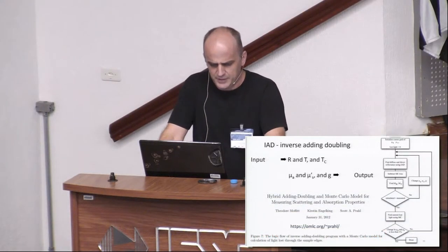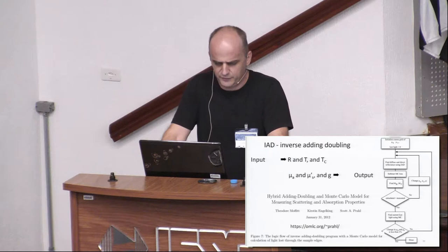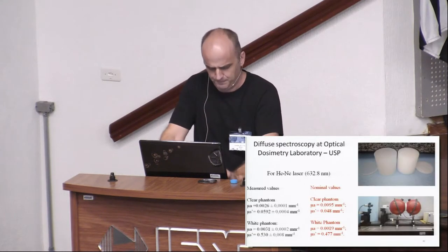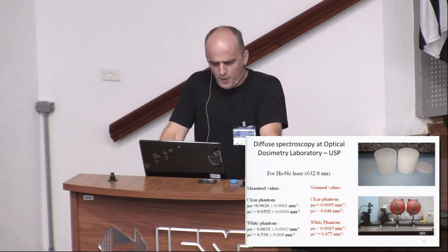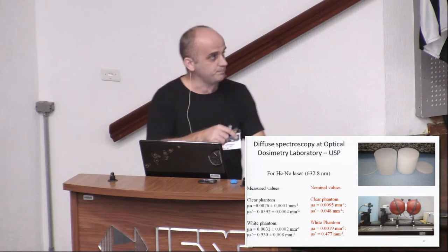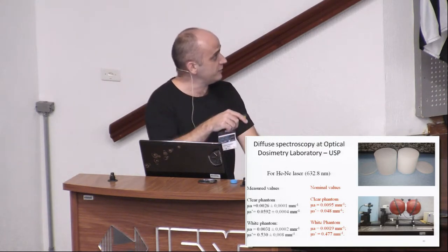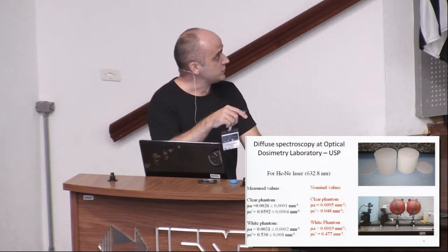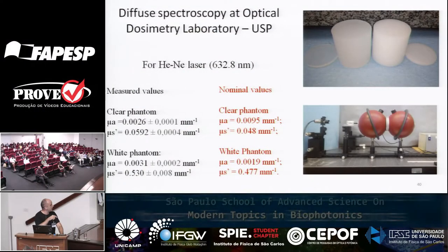Here is the reference on a nice website. We have a lot of information about this algorithm. At the moment, we have a calibrated phantom from Professor Scott Prahl, and we compared the nominal values, and here are our measurements. We have some correspondence with what was measured with our system. This is for a measurement for only one wavelength.